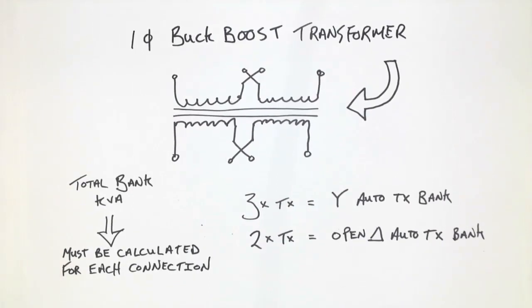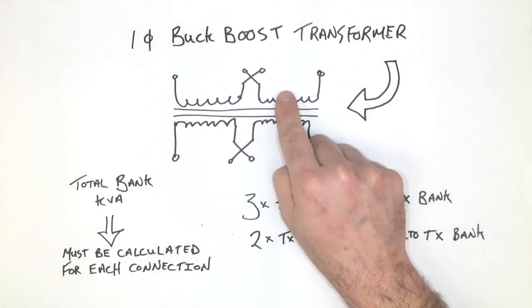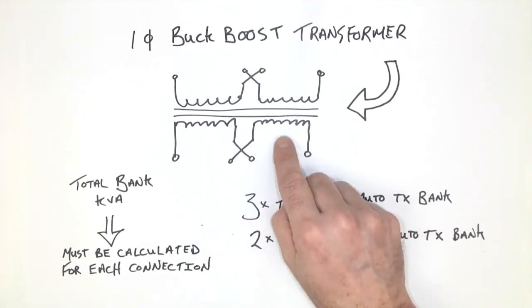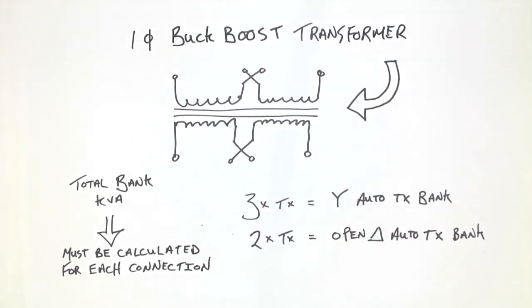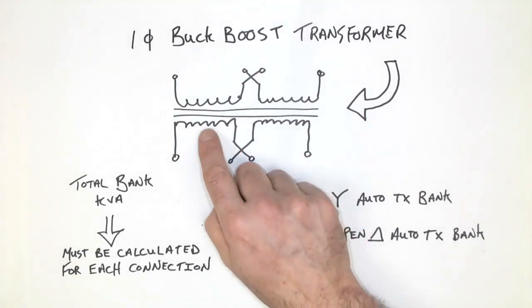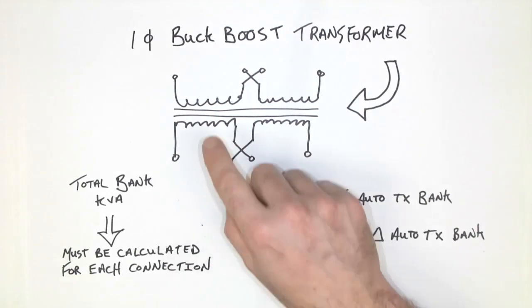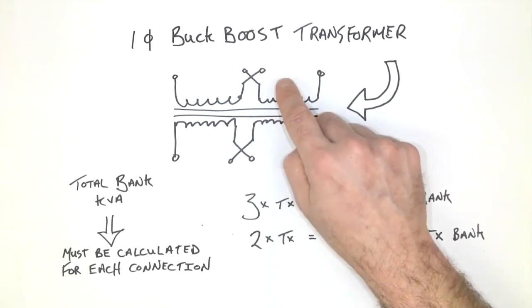It's a multi-winding transformer that typically has identical primary and identical secondary windings in its construction. It's usually isolation, meaning there's no electrical connection between the primary and the secondary windings. And the VA of the entire transformer, if divided by 2, would then give us the VA rating of each of these individual windings.